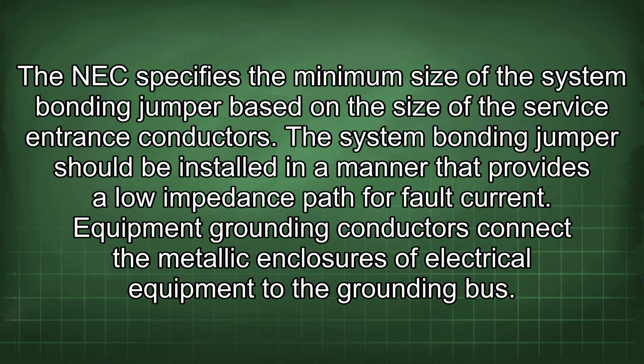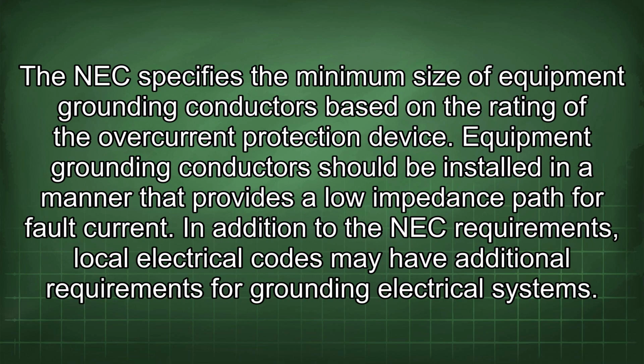Equipment grounding conductors connect the metallic enclosures of electrical equipment to the grounding bus. The NEC specifies the minimum size of equipment grounding conductors based on the rating of the overcurrent protection device. Equipment grounding conductors should be installed in a manner that provides a low impedance path for fault current.